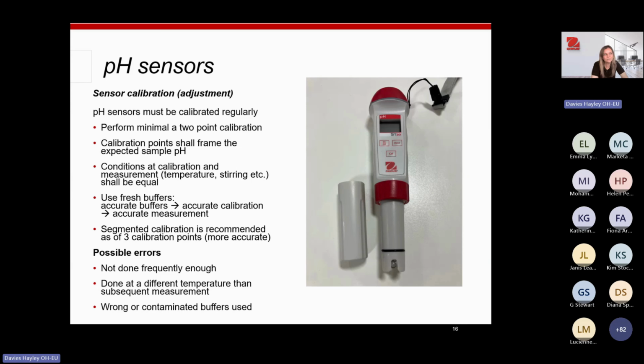It's generally advised, if you know the expected pH of the solutions you're going to be sampling, to try and do your pH points either side. So if you're measuring something of pH 7 in value, then you can calibrate it at pH 4 and pH 10, just to encompass the expected pH of the sample.